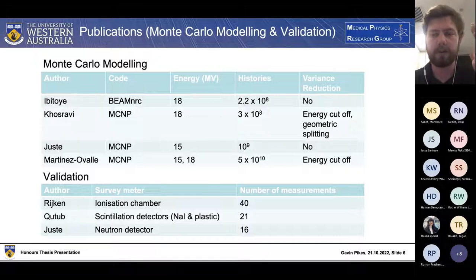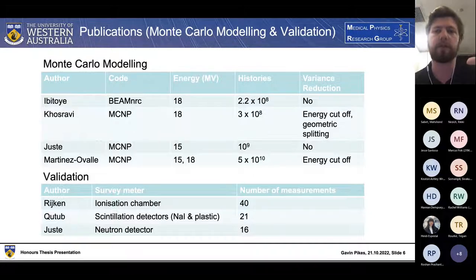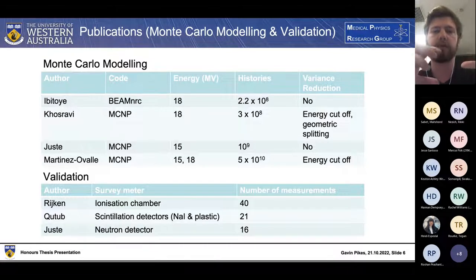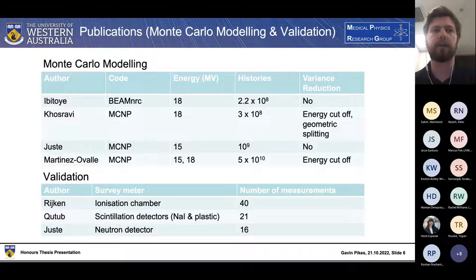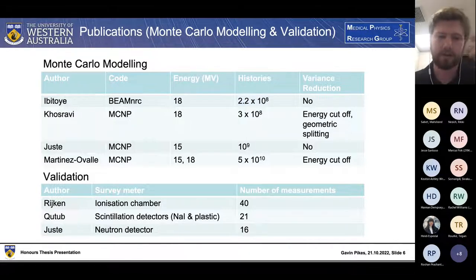The most popular validation method in the literature is to place survey meters within the bunker and compare results to the Monte Carlo simulation. Ideally we'd also look at radiation survey results from the commissioning of the linac bunker, but as these take measurements from outside the bunker room, the uncertainty becomes very high in the simulated results, as only a couple of particles in a billion are actually reaching the detectors being simulated.